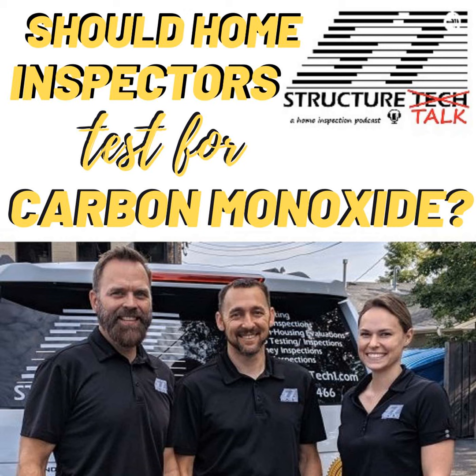It's going to be a matter of taking your metal probe and sticking it up inside there and testing cell number 1, and then wait till you get a good reading, move it over, test cell number 2. And you got to test every one of those different cells because you're sticking your probe in before it mixes with the air at the draft hood. You can't just stick it in the flue.